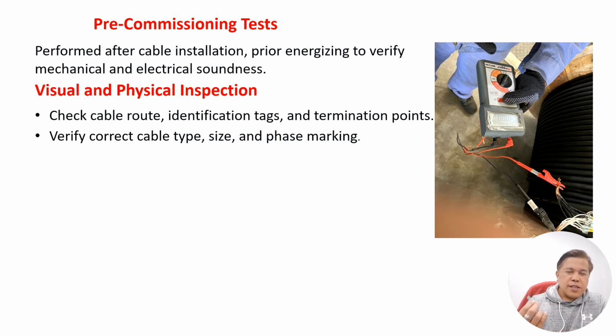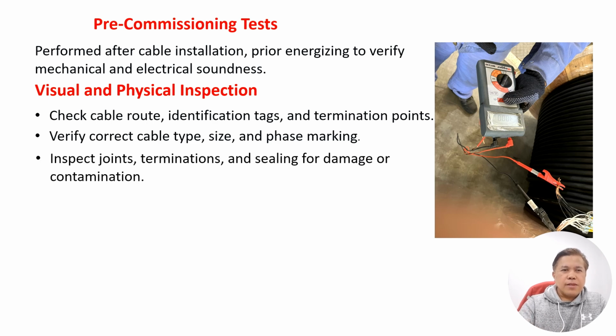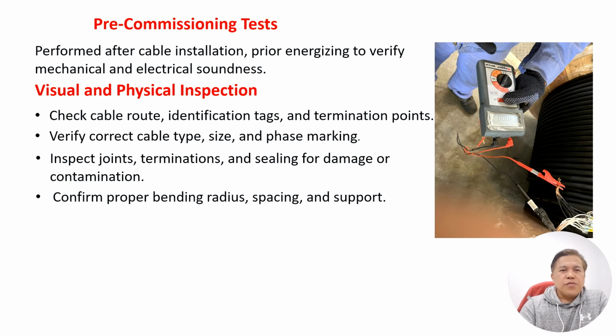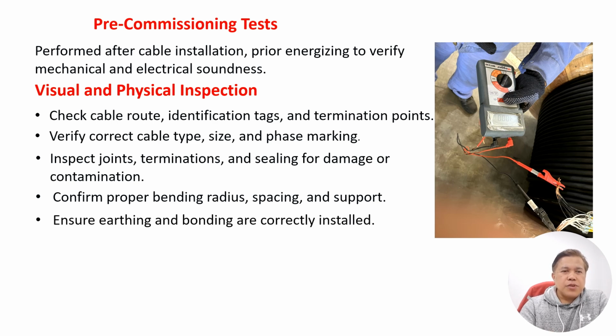So where is this based? On the basis of your approved drawing. All right, so you need to inspect the joints, terminations, and sealing for damage or any contamination. Confirm proper bending, spacing, and support. Ensure earthing and bonding are correctly installed.